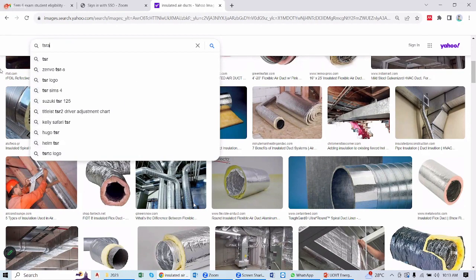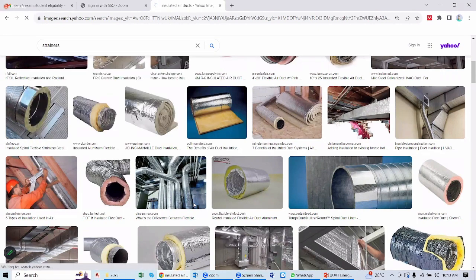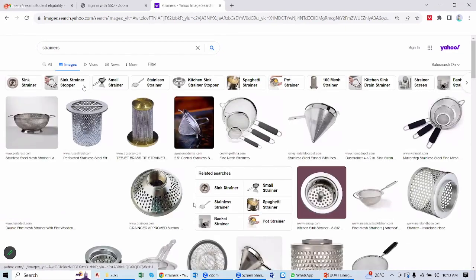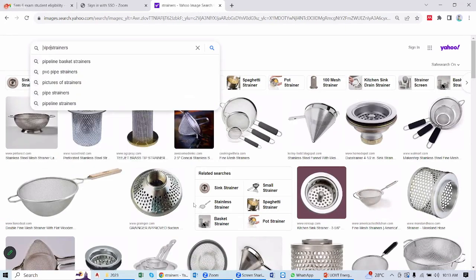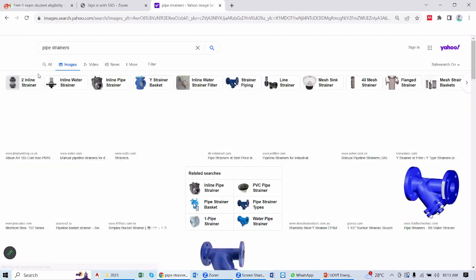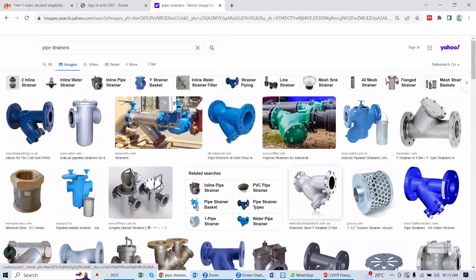They are actually called strainers, not this. So these are called strainers which you install in pipes. There is a direction to install. You will get the arrow mark somewhere here. Generally they are installed before the pump, to ensure that the pump is not getting the impurities coming from the line.